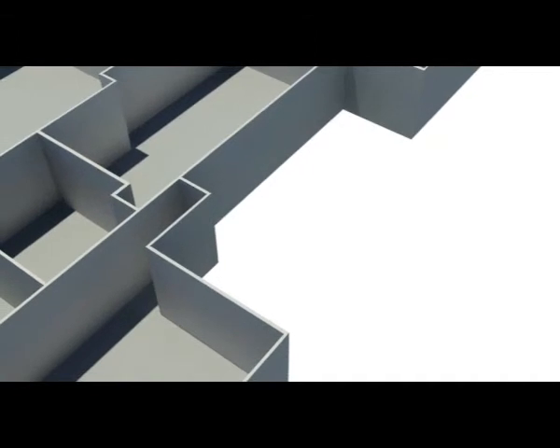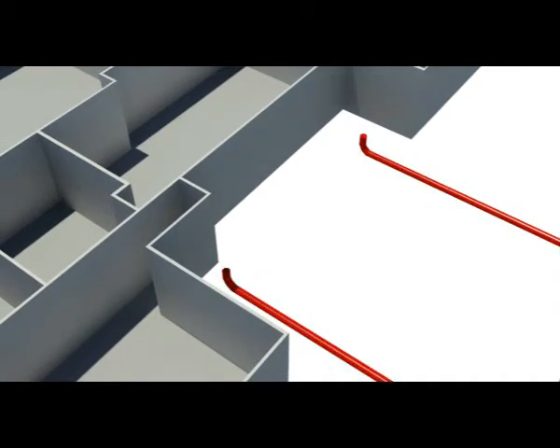Commercial power is delivered to this facility through two separate feeds. This dual power bus configuration is conditioned by 6 UPS units, 4 400 kVA Liebert units, and 2 150 kVA Liebert units. These units provide a true redundant A and B feed to the raised floor.